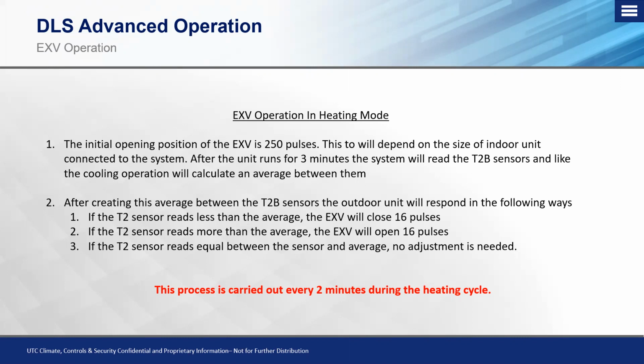So if that T2 sensor reads less than the average, so it's colder, or warmer, excuse me, that EXV will close 16 pulses. Okay, if that T2 sensor reads more than the average, we talk about being a warmer temperature. It's now going to open up 16 pulses because we don't need that indoor coil that warm. So we're going to allow more flow. Okay, it's just the inverse of the AC. Okay, so that's going to be the basic operation between the EXV and the cooling mode and how it controls, and the EXV operation in the heating mode and how it controls.